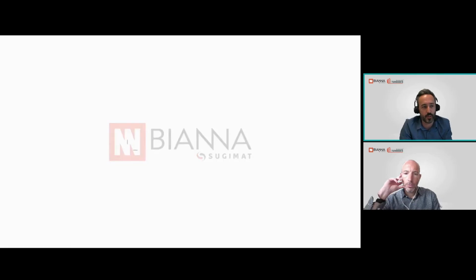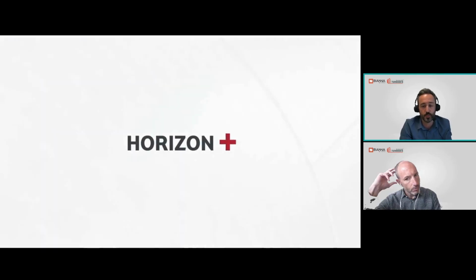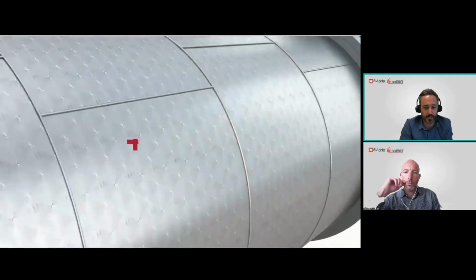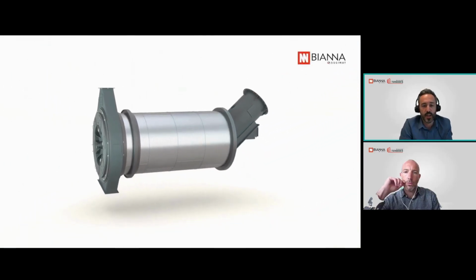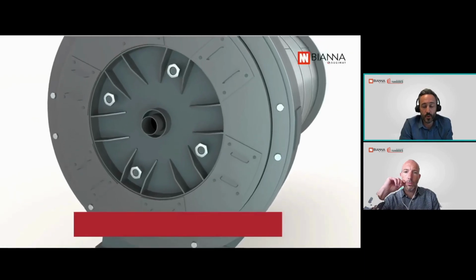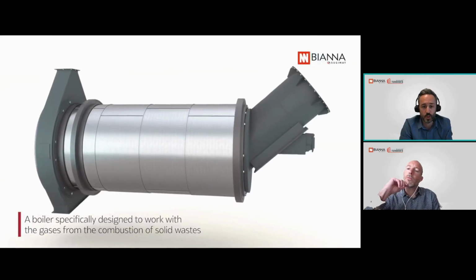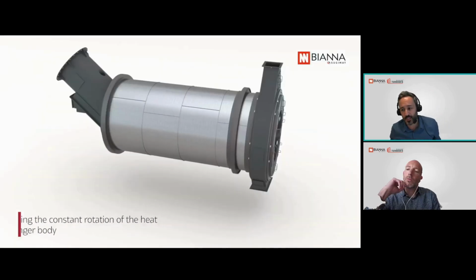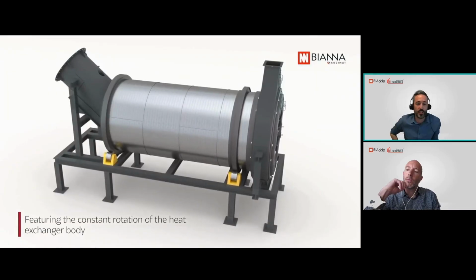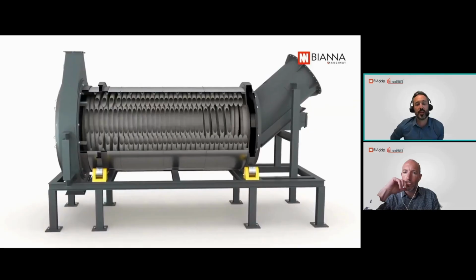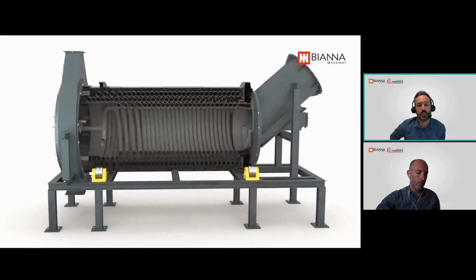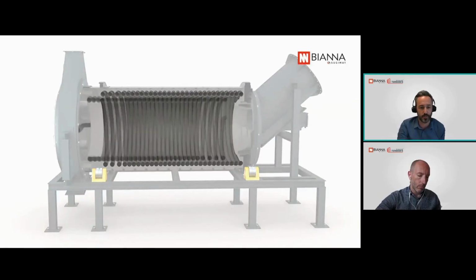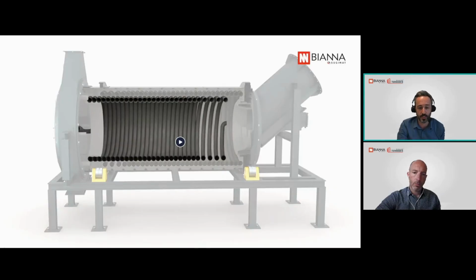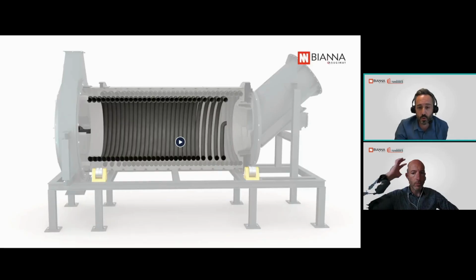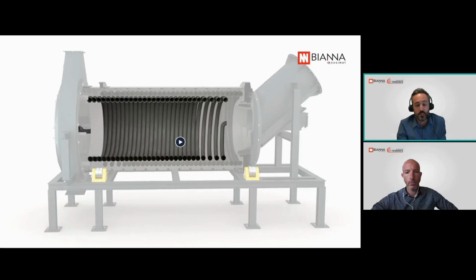The issue in these kinds of systems is the inerts, the impurities contained in the fuel—especially fuels like RDF, which have from 15 up to 25% of these inerts. When combustion starts, these inerts go into the flue gas stream in the form of ashes, causing different problems in the heat exchangers of the boilers.